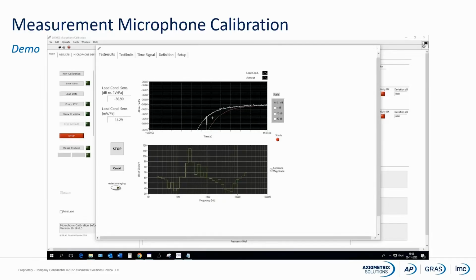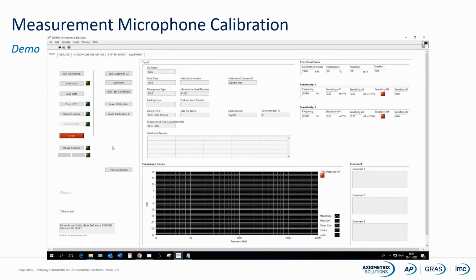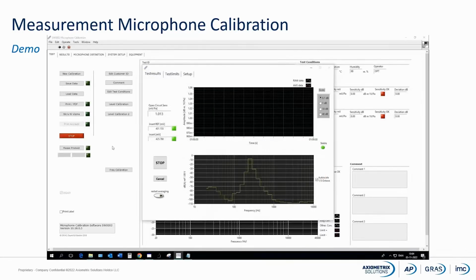We have two curves here, a white curve and a red curve. The white curve is an instantaneous curve, while the red curve is an average curve. I just made a little knock on the table, and you can see that the microphone could hear that. The instantaneous curve went very, very high, and the average a little bit higher. The stabilization light is green, and we will wait a little. Normally, I will wait about half a minute to ensure that everything is okay.